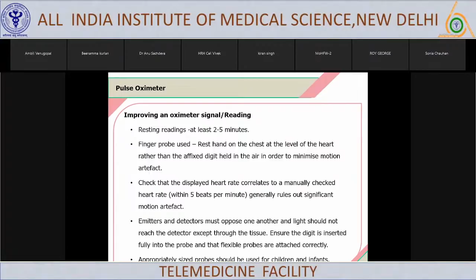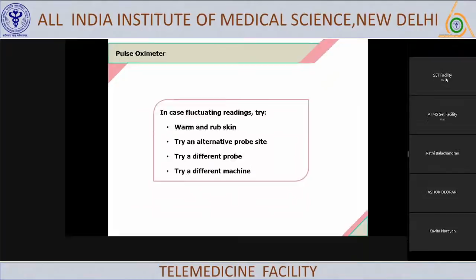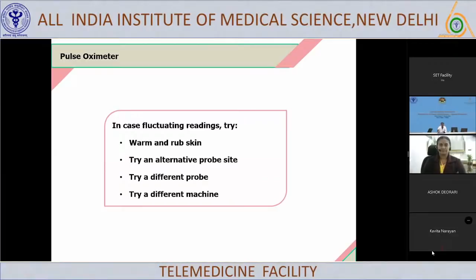In case sometimes you will see that when you apply the pulse oximeter, the readings will fluctuate. You will see it showing 97, but then it will show 85 and then will come back. Usually the patient will not show so much fluctuation clinically without intervention, so this means this is a technical error. In those cases, ensure that the patient's finger is warm. You can rub the skin. Try an alternate probe site. You can keep it on the other hand. You can keep it on the foot also. Try a different probe and check your equipment also.